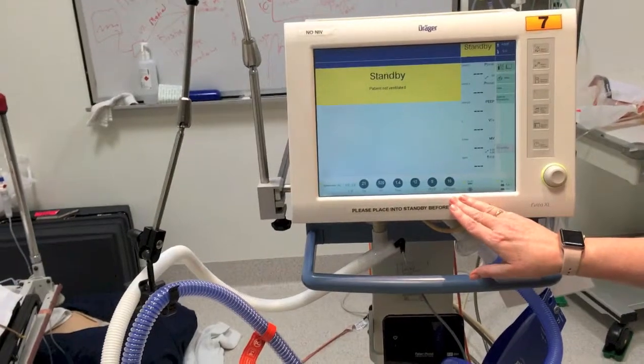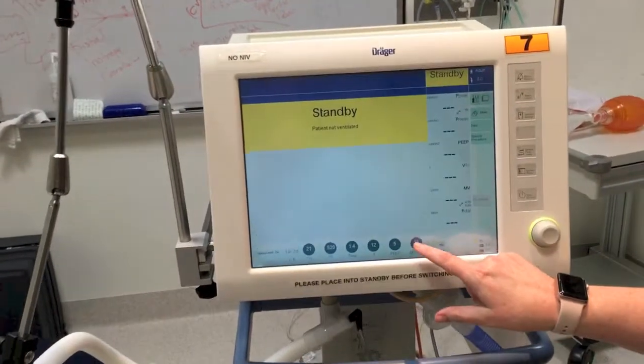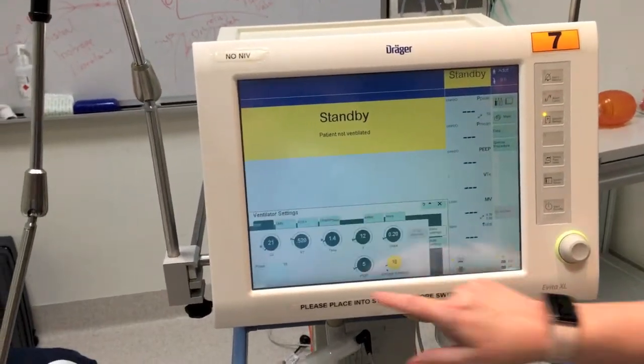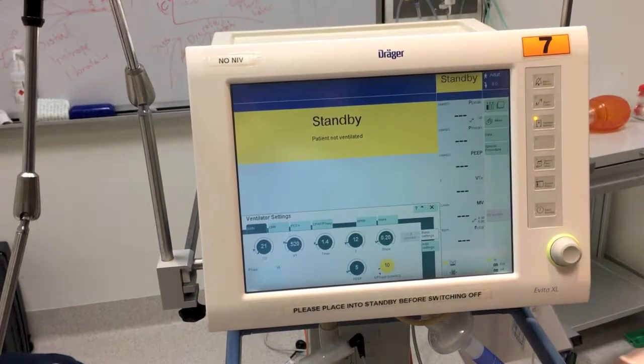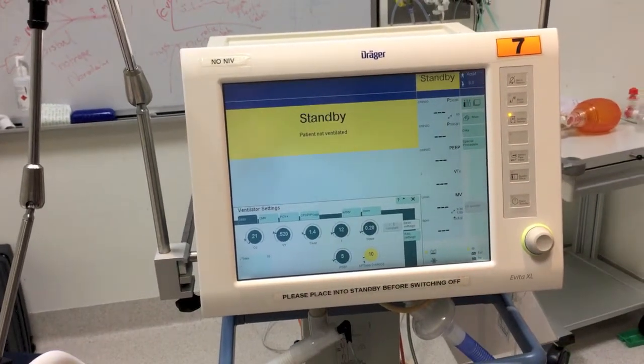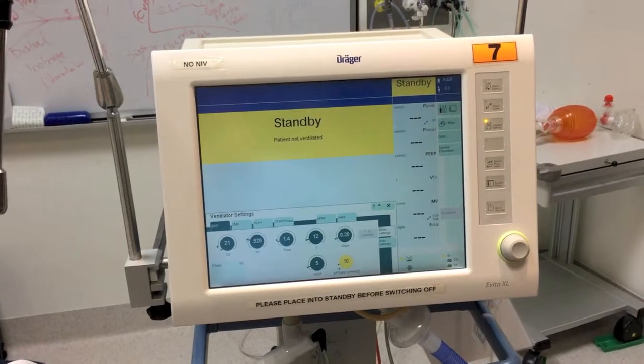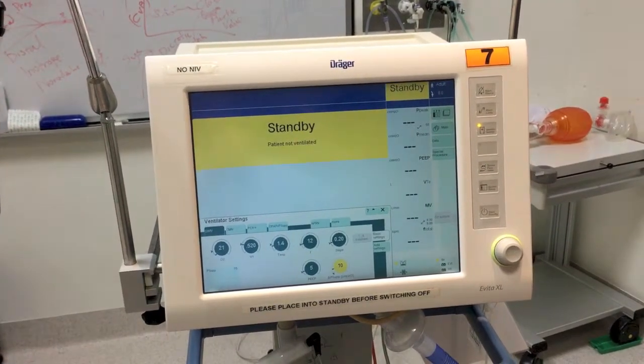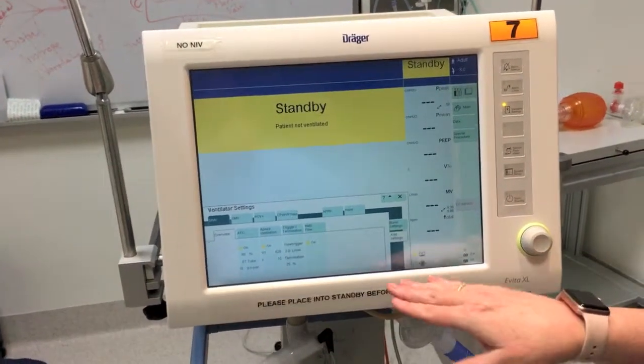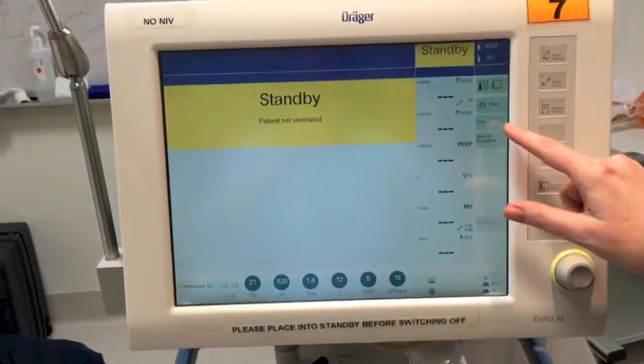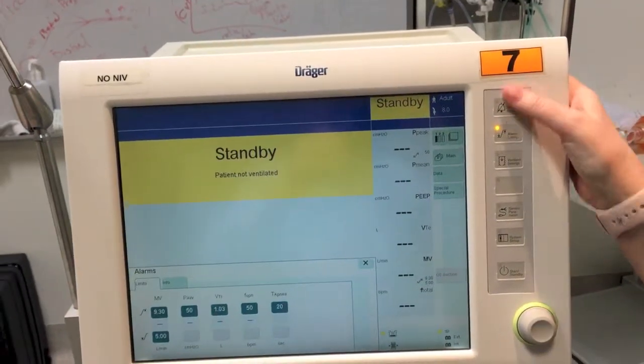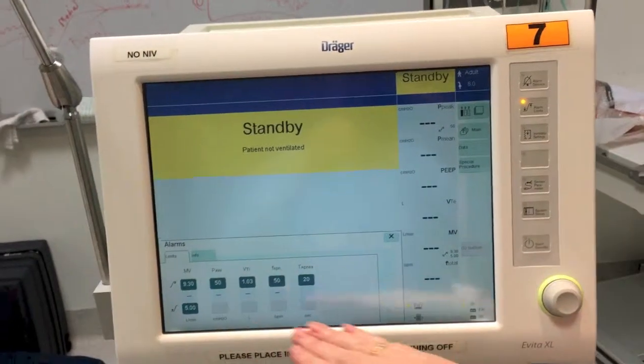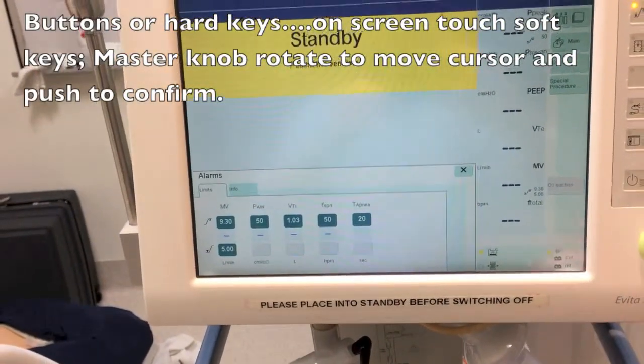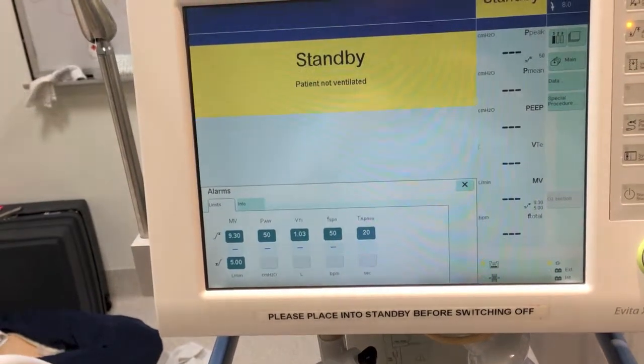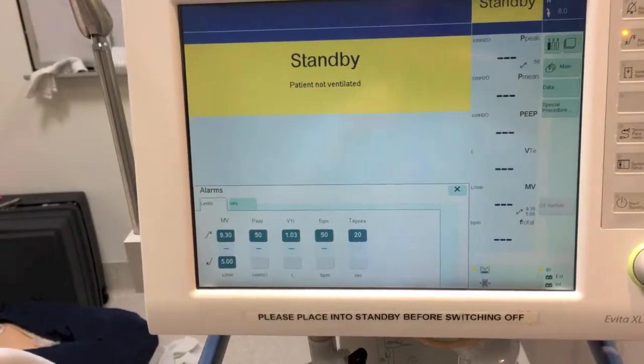You can see the settings are down the bottom here, and you can adjust them by tapping on those. Our standard setting would be SIMV, volume control ventilation, and you can see the settings that are on there. It's got the additional settings page just behind that, and you can go to alarm limits on the hard keys here and adjust your alarm limits before you even start getting the ventilator going, if you wanted to get it auto cycling, for example, before a patient arrived in the ICU.